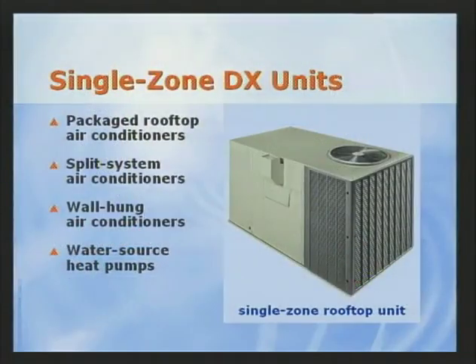And the second system type includes a single DX unit located in or near each classroom. And we'll look at ways to improve the dehumidification performance. Each unit is a basic single-zone constant volume system. Examples of DX units in this category are packaged rooftops, split systems, wall-hung units, and water source heat pumps.